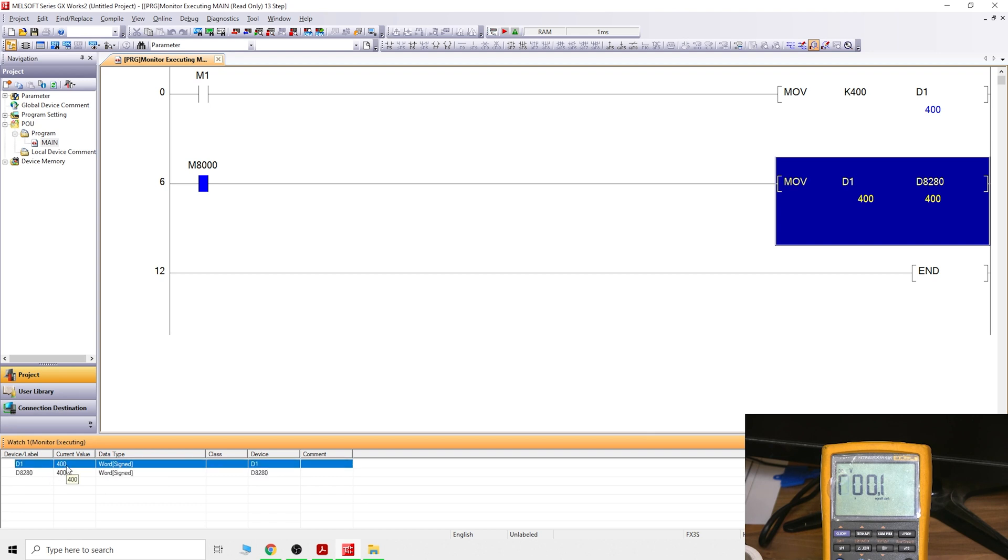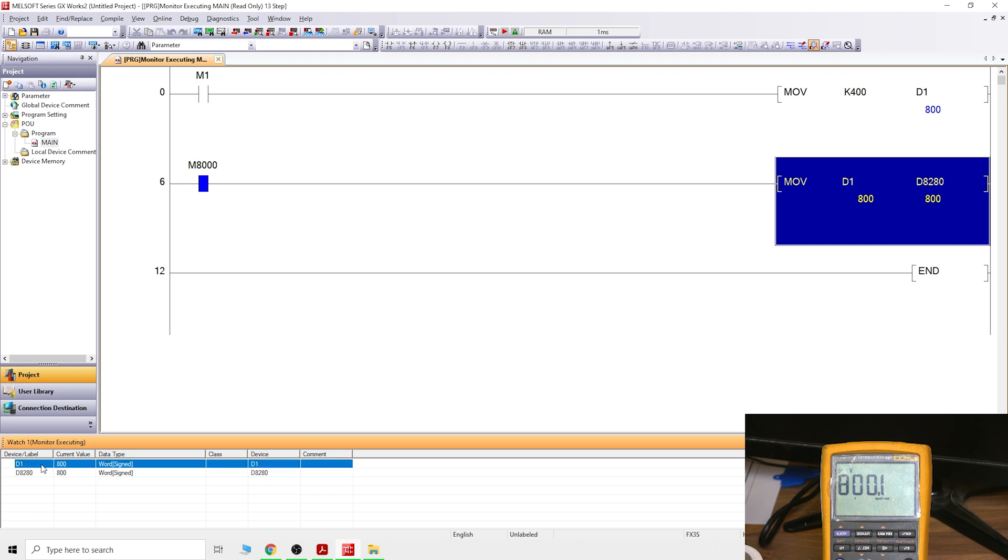But you can edit values in D1 because it's internal. Let's change that one to 800. As you can see, 800 got transferred into D8280, and now we have 2 volts, even though it looks like it's 4 volts. The full 10 volts are at 4,000.